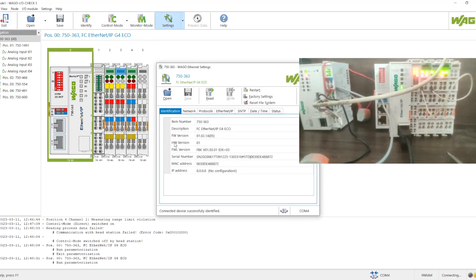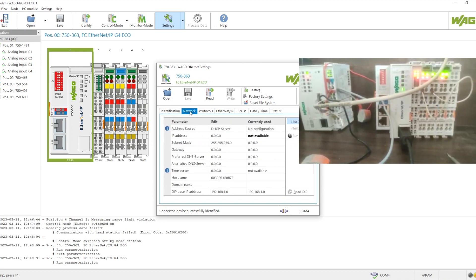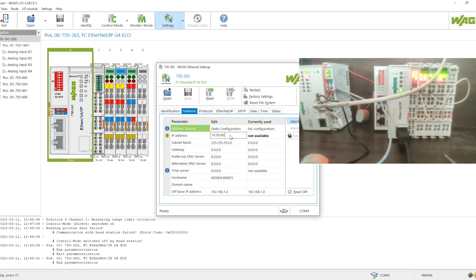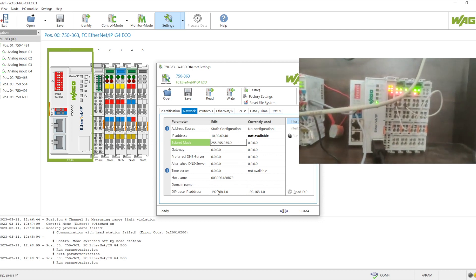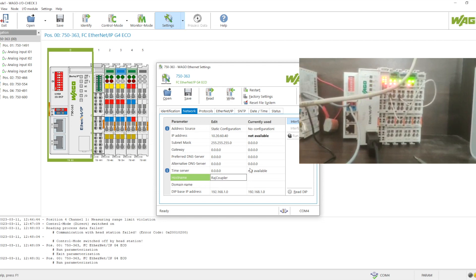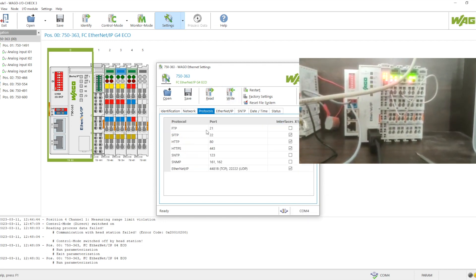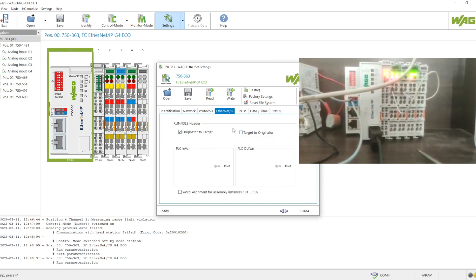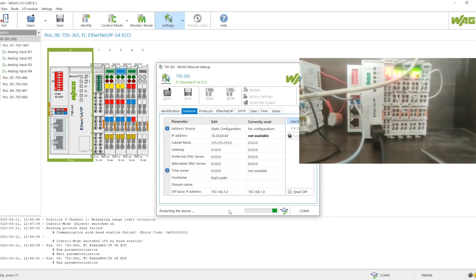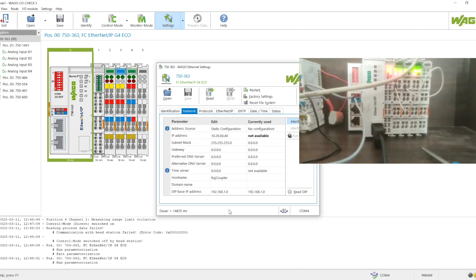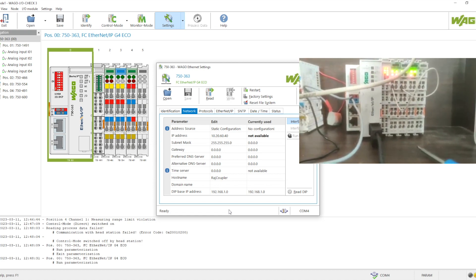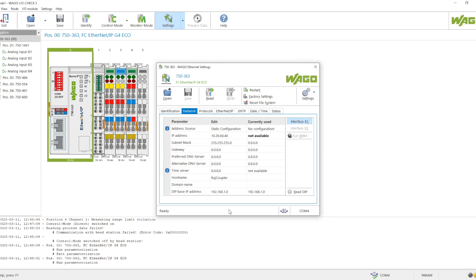For the bus coupler we can do all the settings from within this software. Under the network settings, for example, if it is currently set as DHCP and I want to change it to a static IP, I provide the IP there. I can also change the host name directly from here. After making all the changes, we click 'Write' and it will write the configuration to the coupler or to the controller, depending on what is connected. The process is the same for all devices.